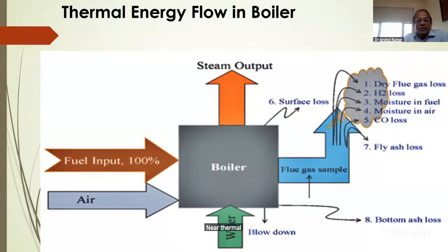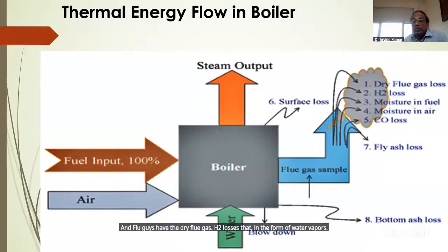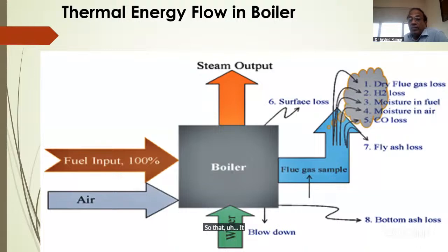There is thermal energy flow in boilers. The energy is taken in the form of coal, oil or gas, and it combusts with air. The output is steam and flue gas. Flue gas has dry flue gas losses, H2 losses in the form of water vapor and moisture in air, and CO losses, carbon monoxide. CO should not be present, but some CO is present in the exhaust gases because of the short time in the combustion process. So we add some excess oxygen, so that CO is nil or suppressed.